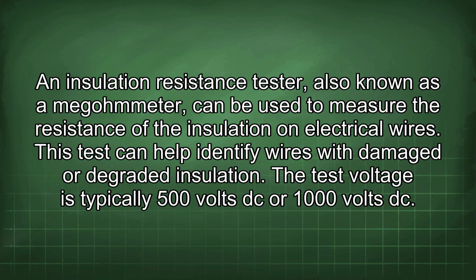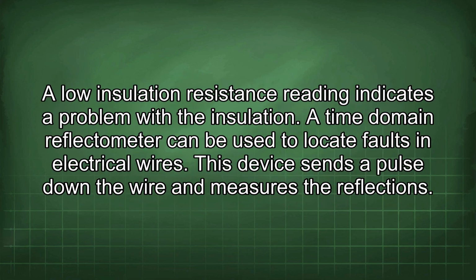An insulation resistance tester, also known as a megohmmeter, can be used to measure the resistance of the insulation on electrical wires. This test can help identify wires with damaged or degraded insulation. The test voltage is typically 500 volts DC or 1000 volts DC. A low insulation resistance reading indicates a problem with the insulation.